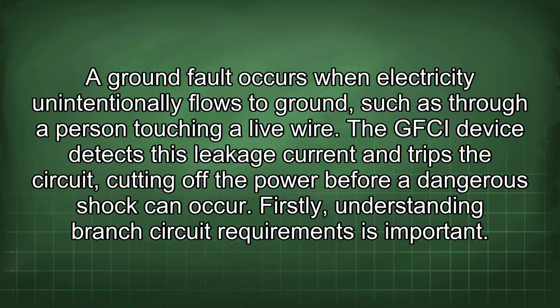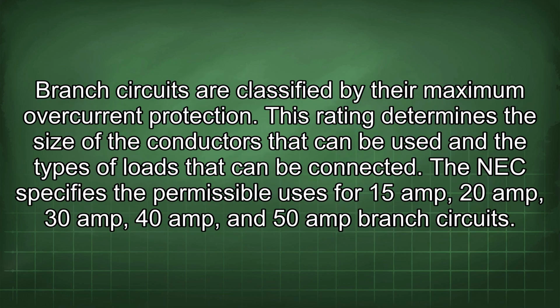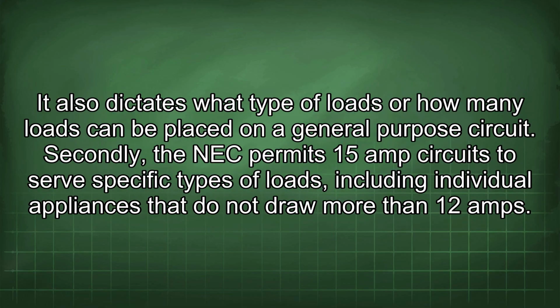Firstly, understanding branch circuit requirements is important. Branch circuits are classified by their maximum overcurrent protection. This rating determines the size of the conductors that can be used and the types of loads that can be connected. The NEC specifies the permissible uses for 15-amp, 20-amp, 30-amp, 40-amp, and 50-amp branch circuits. It also dictates what type of loads or how many loads can be placed on a general-purpose circuit.